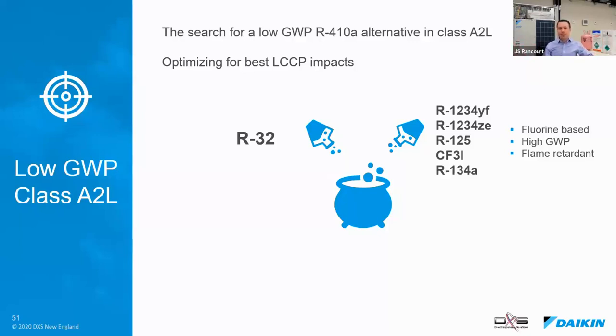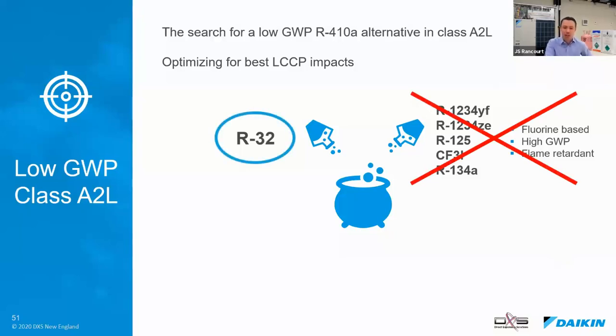What's happening is every time you mix something with our beloved R32, you're doing something bad to it. You're making it less efficient. You're making it conduct less heat, needing more of it. You're raising the GWP. So essentially, what's happened globally, and it's almost fully agreed upon, is that you just got to stop mixing things with it. And R32 is essentially becoming the go-to A2L refrigerant of the future.